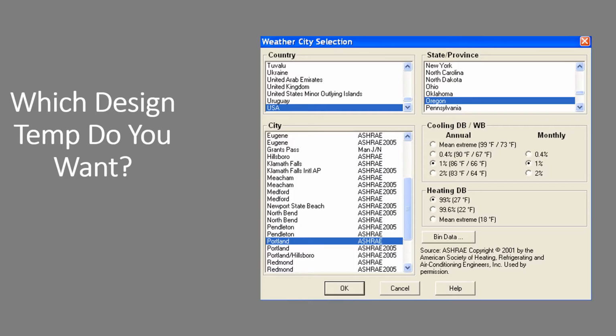Please notice that on the cooling design temperatures, they give you a few options. The 2%, that would be only 2% of the time does it get above 83 degrees. The 1% is 86. The 0.4 is 90. Well, summers are getting warmer and summers are getting smokier. The mean extreme is 99. I think that you would be fine, quite honestly, in climates such as Portland, Oregon, where there is a big gap between the average summer temperature and our mean extreme. I think you'd be fine using this 0.4 at 90, or maybe in some cases the mean extreme. But I would never use these 2% or 1%.